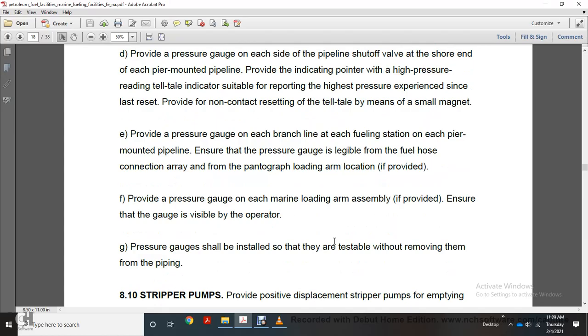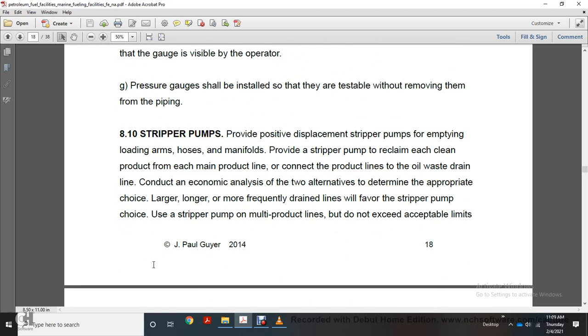Ensure the pressure gauge is legible from the fuel hose connection array and from the loading arm location. Provide a pressure gauge on each marine loading arm assembly. If provided, ensure the gauge is visible by the operator. Pressure gauges should be installed so that they are testable without removing them from the piping.